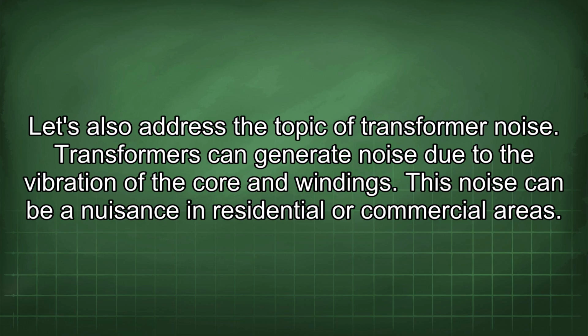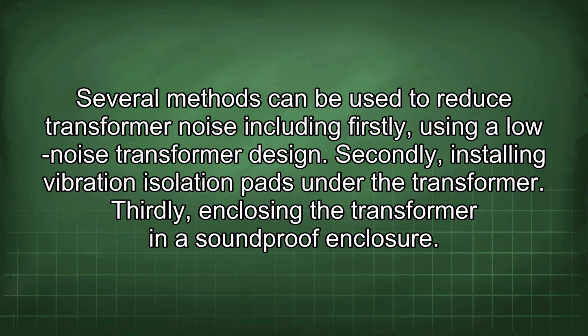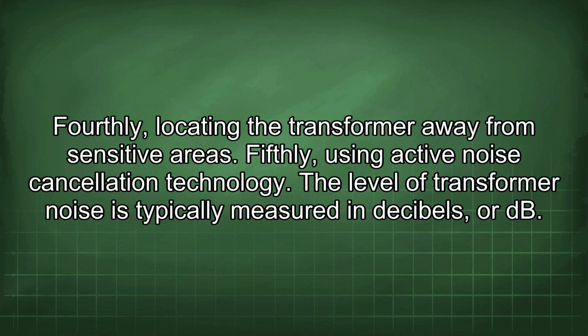Let's also address the topic of transformer noise. Transformers can generate noise due to the vibration of the core and windings. This noise can be a nuisance in residential or commercial areas. Several methods can be used to reduce transformer noise, including, firstly, using a low-noise transformer design. Secondly, installing vibration isolation pads under the transformer. Thirdly, enclosing the transformer in a soundproof enclosure. Fourthly, locating the transformer away from sensitive areas. Fifthly, using active noise cancellation technology.